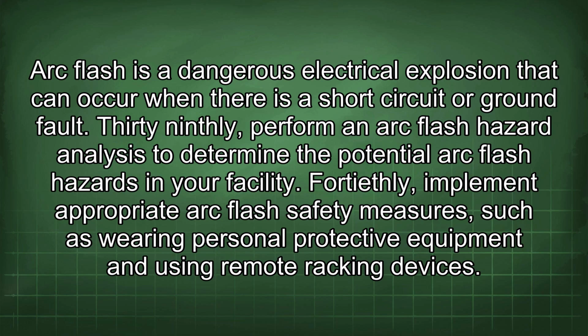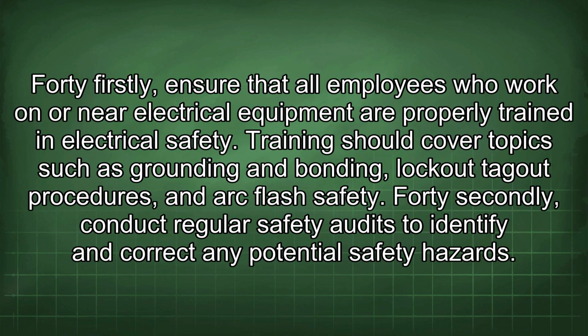39thly, perform an arc flash hazard analysis to determine the potential arc flash hazards in your facility. 40thly, implement appropriate arc flash safety measures such as wearing personal protective equipment and using remote racking devices. 41stly, ensure that all employees who work on or near electrical equipment are properly trained in electrical safety. Training should cover topics such as grounding and bonding, lockout-tagout procedures, and arc flash safety.